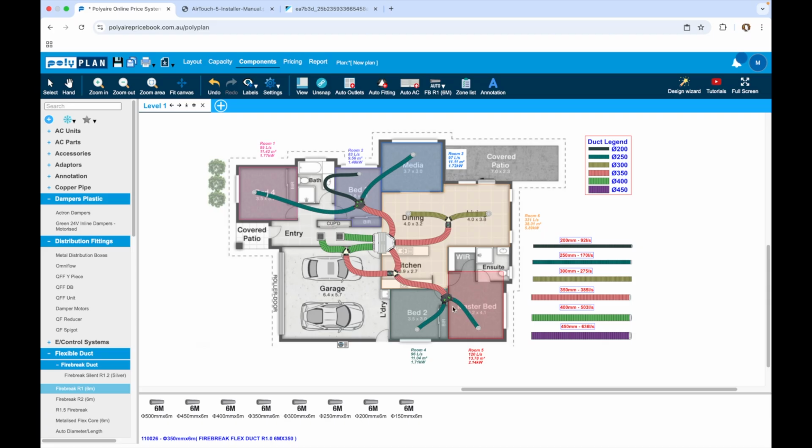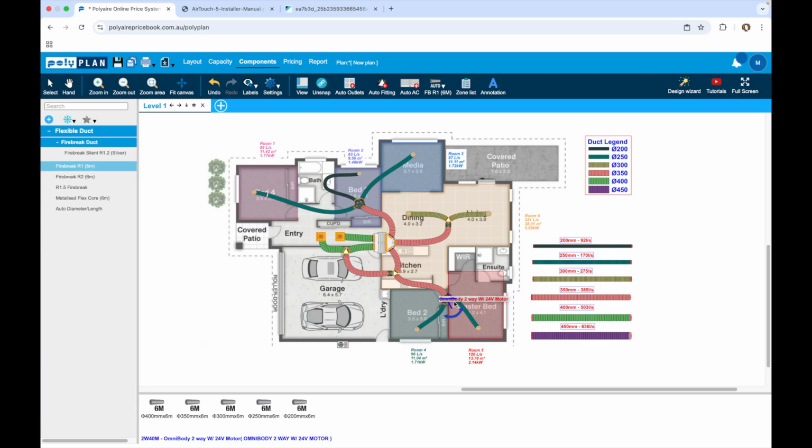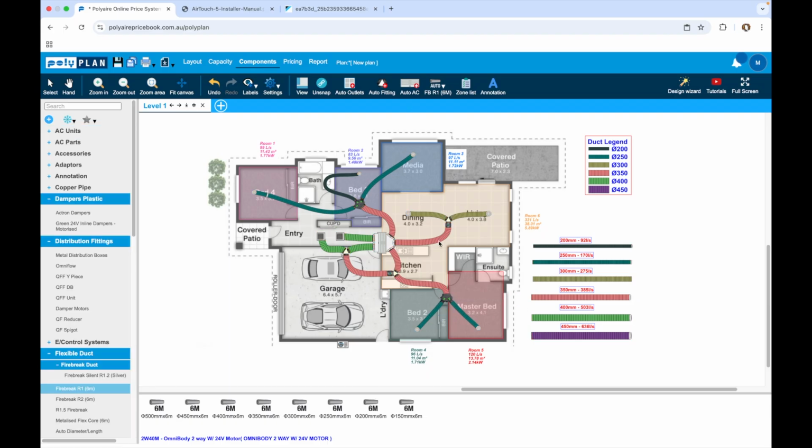The problem with spill zones is that when you start using them with things like Airtouch 4s and Airtouch 5s or MyAirs, or any of that stuff where they have temperature sensors, they tend to run longer than what people want them to, and they create levels of discomfort for people. The way a spill zone works is it typically opens based on a calculation of the percentage of your zones that are on and how far they're open.